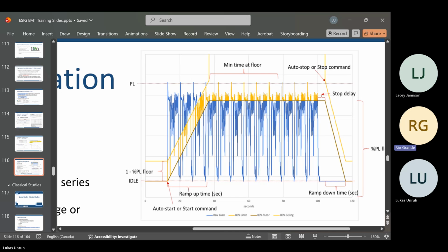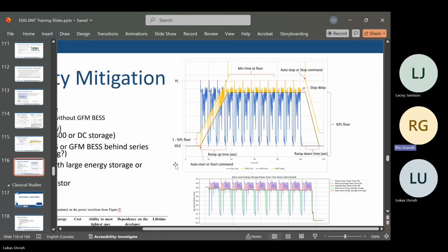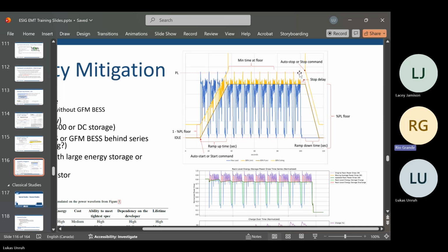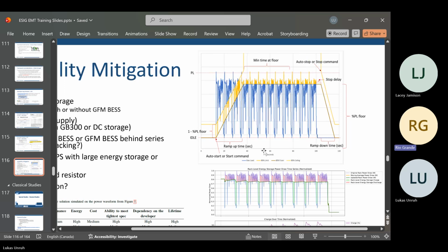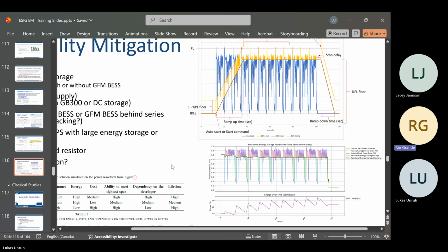This is all great in terms of the total variation, but the band on top of the brown curve here might be where all the harmonic content is that you're worried about. Depending on the machines nearby and the network connections and all that stuff, you might still have a significant problem even in this harmonic content just at the top here, or subharmonic, I should say. But this method can be used to really avoid a whole bunch of the fluctuation.